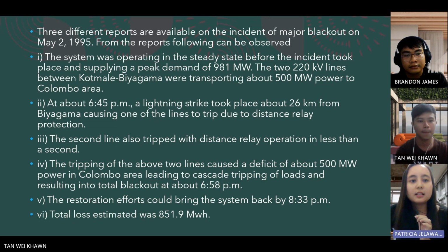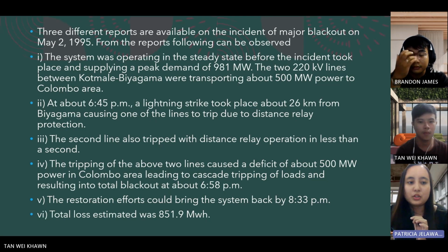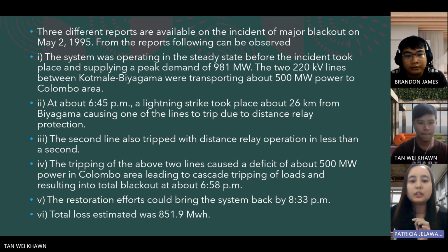Second, at about 6:45 p.m., a lightning strike took place about 26 kilometers from Biyagama, causing one of the lines to trip due to distance relay protection. Third, the second line also tripped with distance relay operation in less than a second. Fourth, the tripping of the above 2 lines caused a deficit of about 500 megawatt power in the Colombo area, leading to cascade tripping of loads and resulting in total blackout at about 6:58 p.m. The restoration efforts could bring the system back by 8:33 p.m. Total loss estimate was 851.9 megawatt hour.